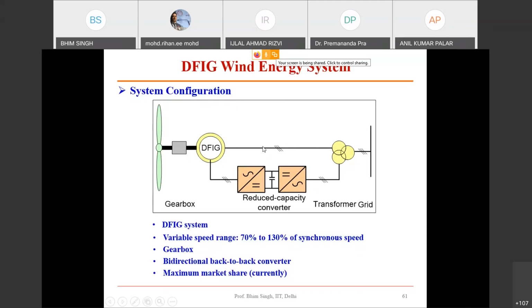Because of this reason, this technology is used. And for these converters, the rotor is normally of low voltage compared to stator voltage, and it runs only 30% slip. So if you consider the rotor voltage is half, and you operate at 30% slip, so 0.3 into half, 0.15, you have only 15% voltage rating of these converters compared to the voltage on the stator side. So 15% voltage means virtually the voltage rating of the devices will be quite low.